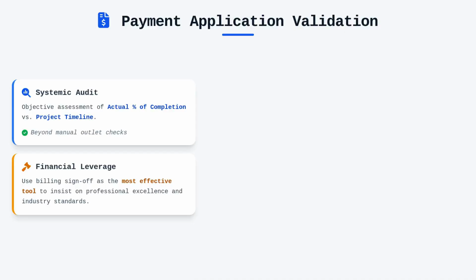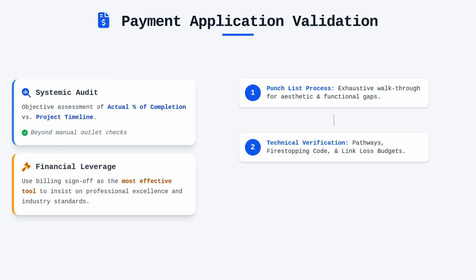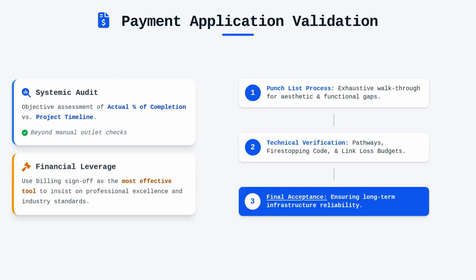When the installation nears completion, you will lead the punch list process, which is a formal, exhaustive walkthrough to identify aesthetic and functional deficiencies that must be rectified before final acceptance. This includes verifying that pathways are properly supported, firestopping is correctly installed according to the code, and all terminations are documented and tested against the link loss budget. By maintaining this level of authority, you ensure that the project is not just completed, but completed to a standard of quality that guarantees long-term infrastructure reliability.